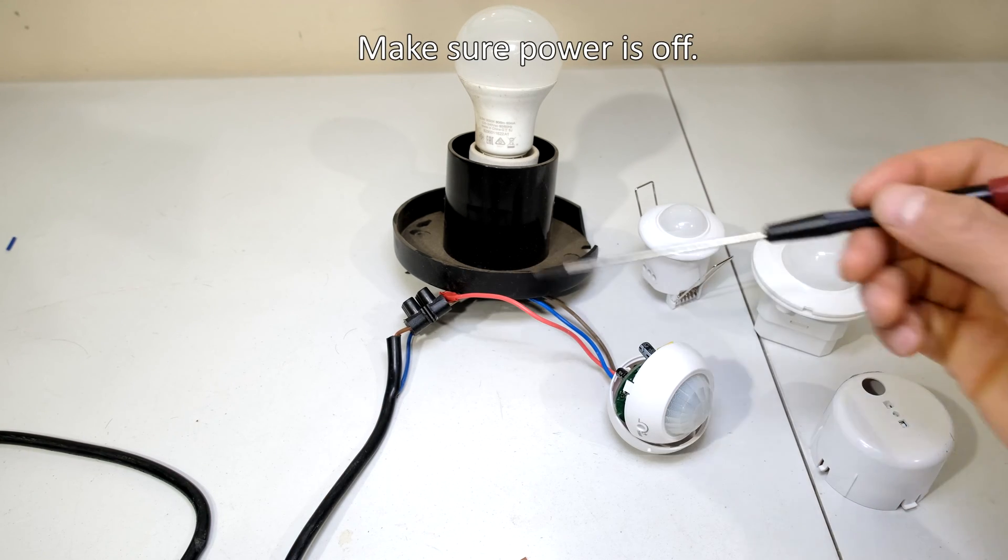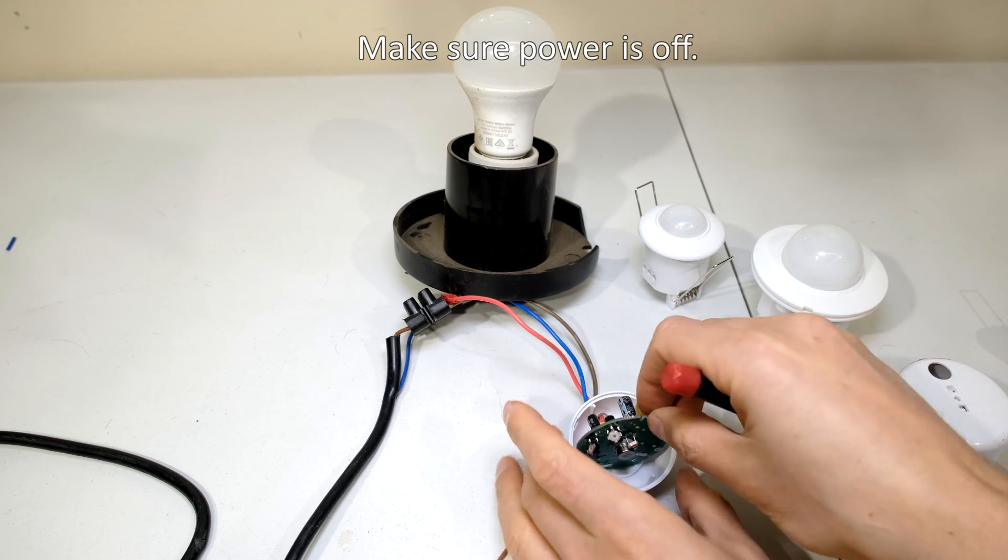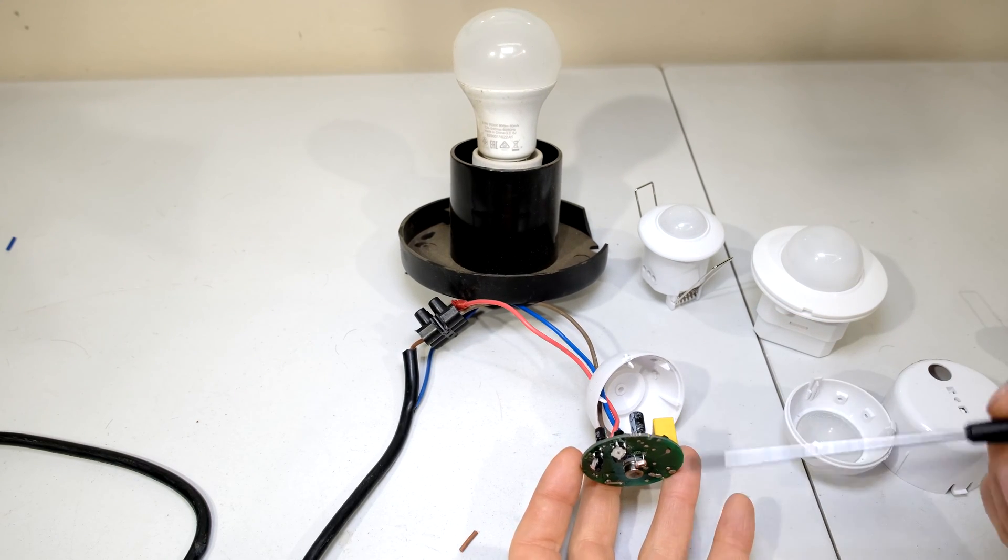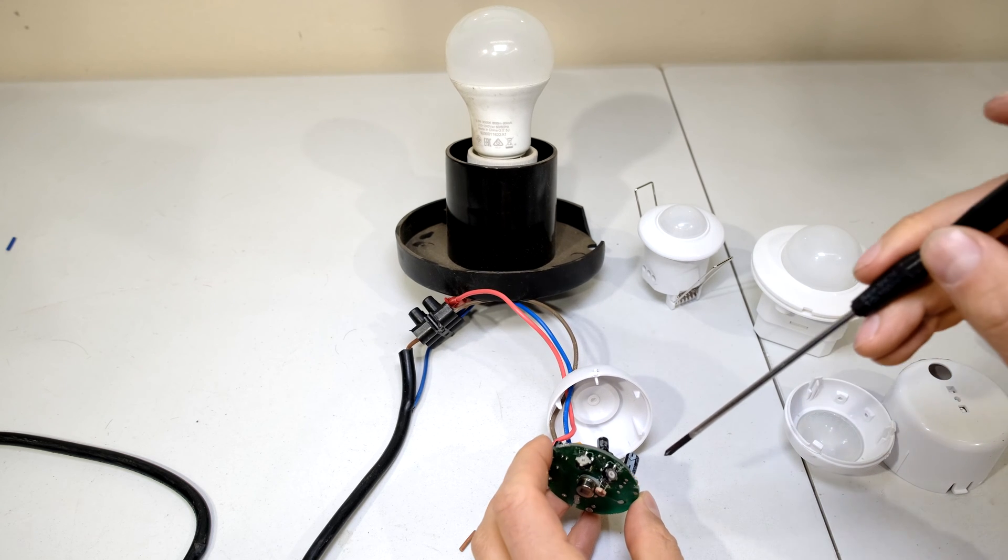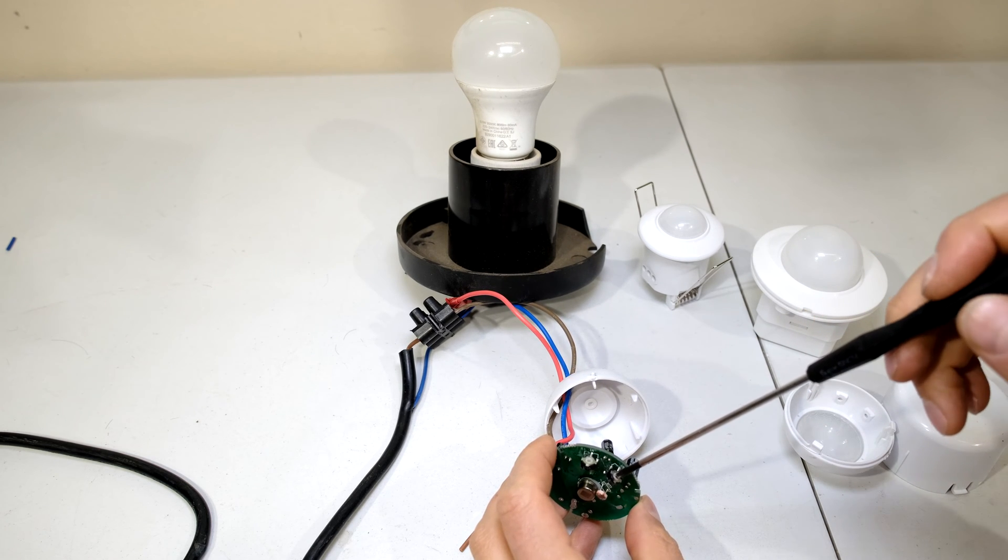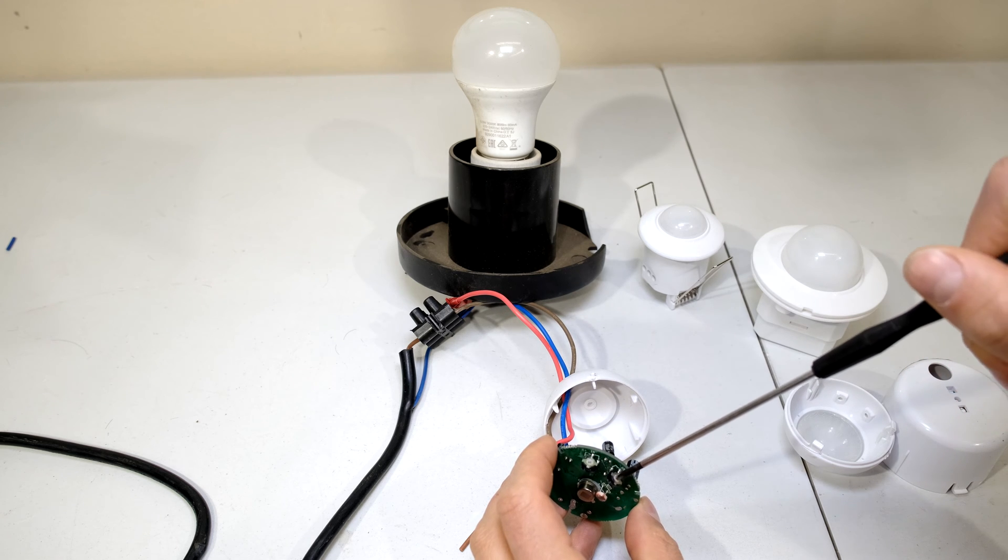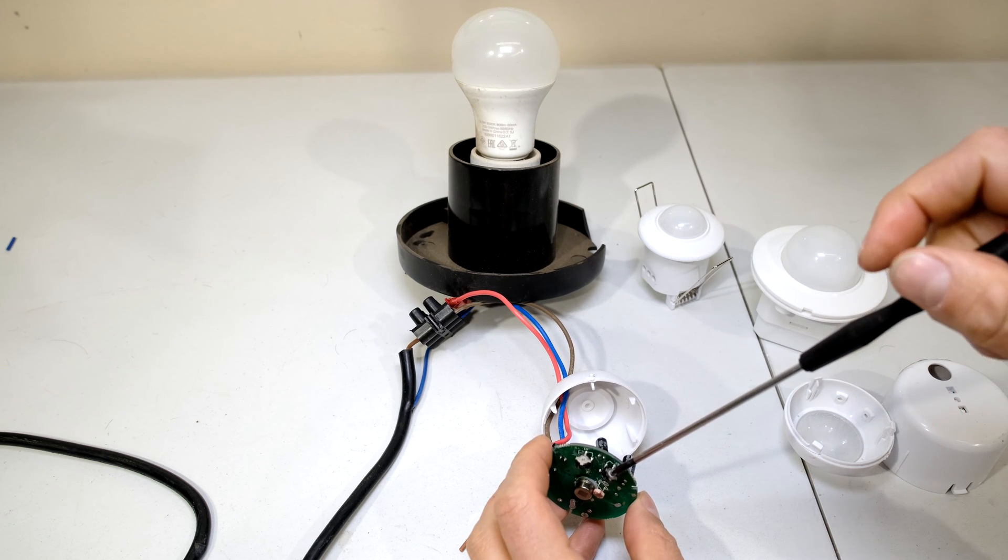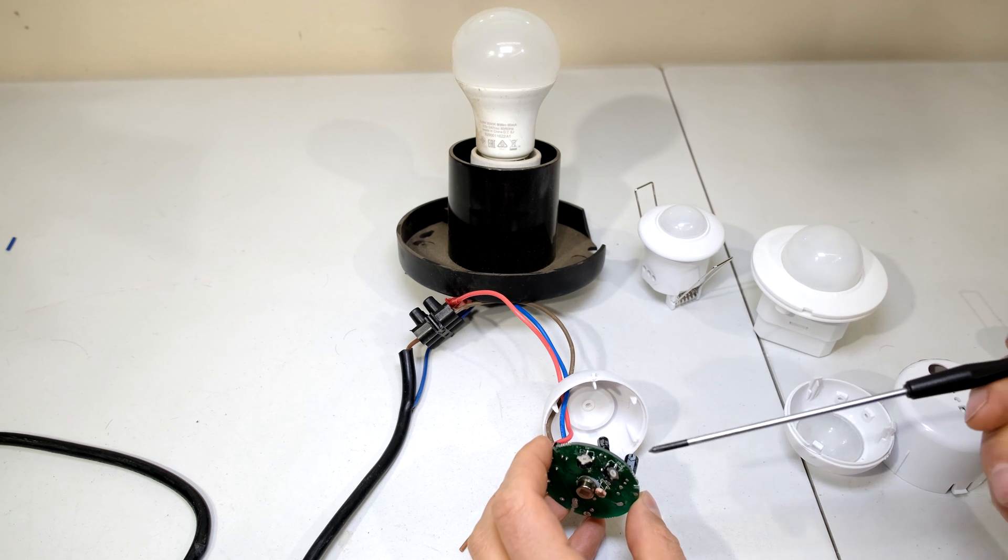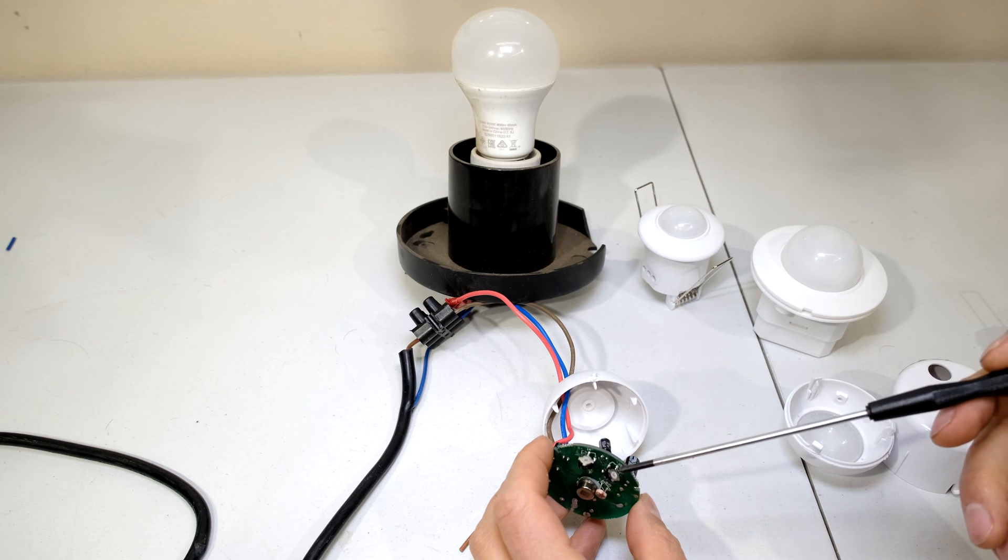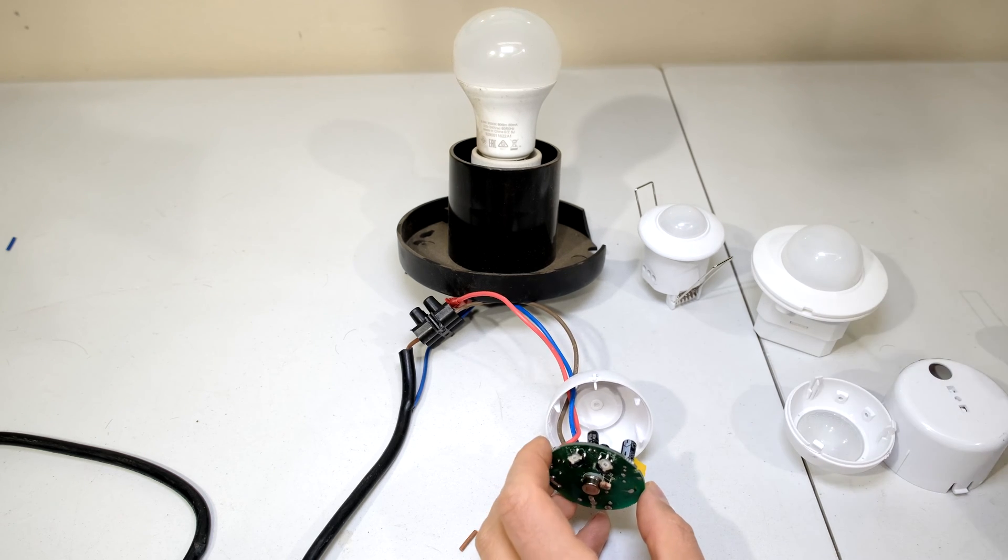Now I've disconnected this from the supply and I'll show you inside here. I've already opened mine and the electricity is now off, so there's no shock hazard while I work on this. Obviously there is an adjustment which you can manually change the timing sequence. For example, that would be the maximum which will give me that five minutes, and the minimum gives me not even 20 seconds. So this is too short and I'd like this to be at least 10 minutes. This is the point of this video.